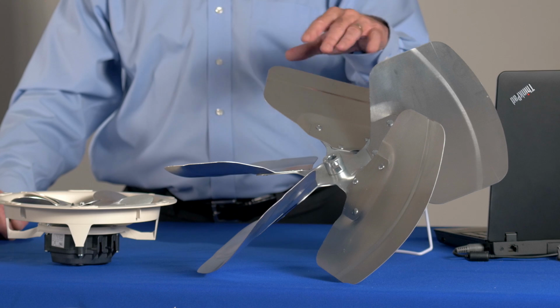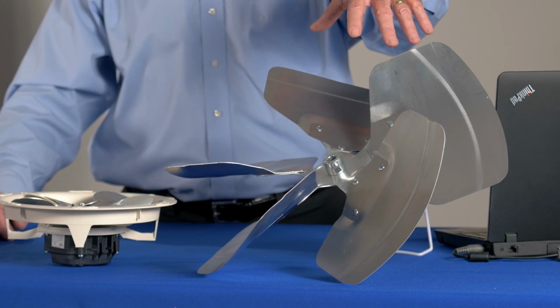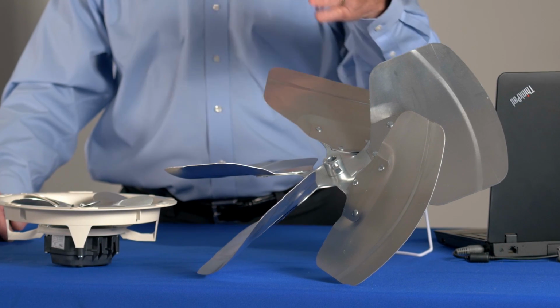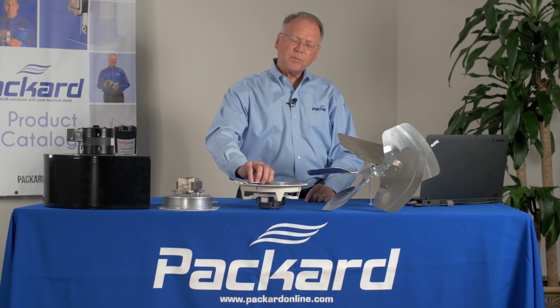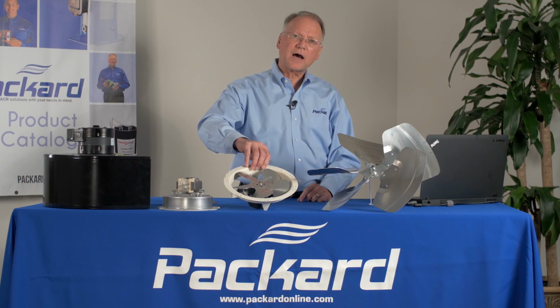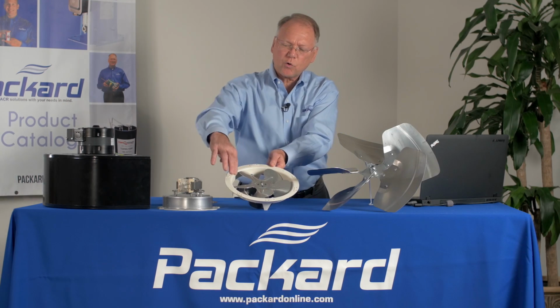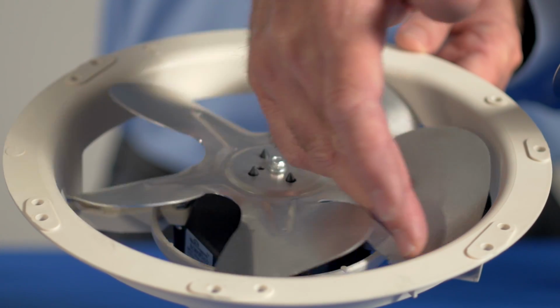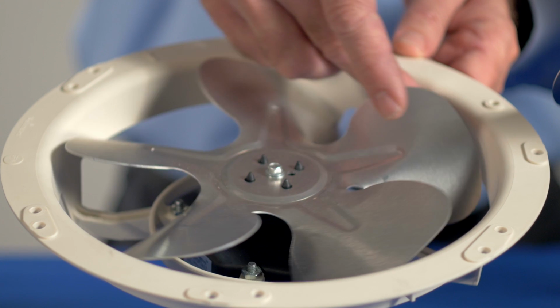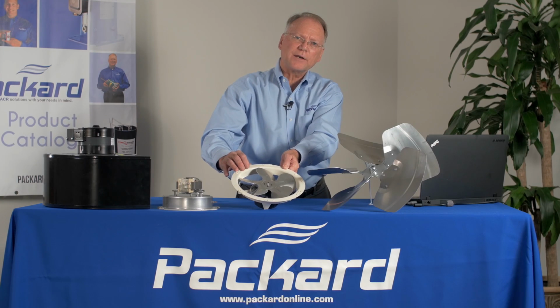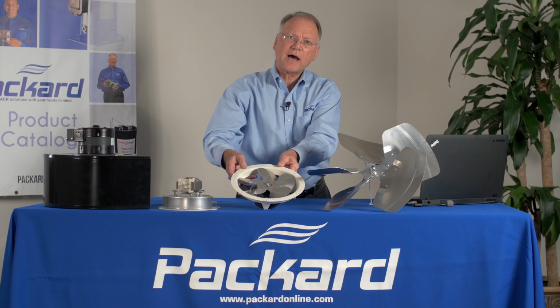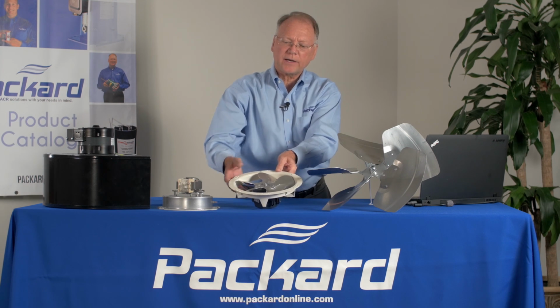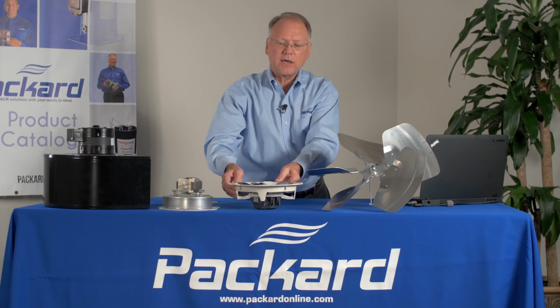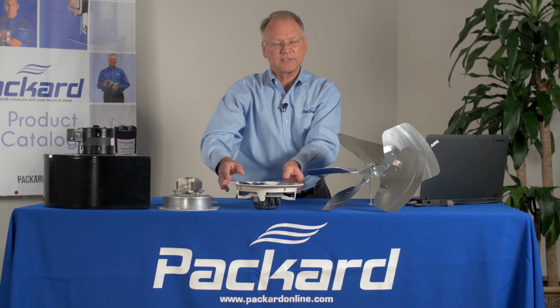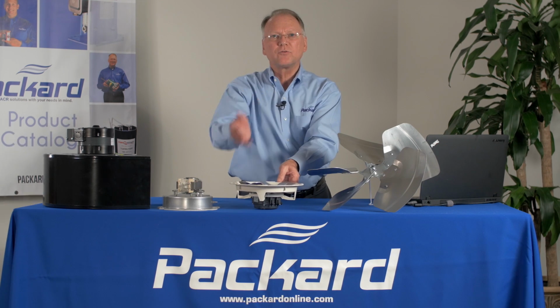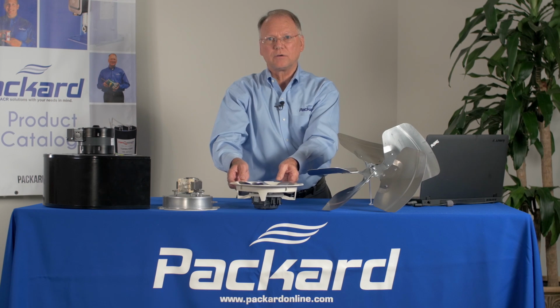One of the key characteristics of the fan or the blades that are on the fan is the pitch that is assigned with the fan. But what is important for the operation of the fan is to have an orifice that helps to direct the air movement through that fan to give it higher velocity, also to provide direction for that so that the air isn't moving off of the sides of the blades instead of going to the location where we want that to go.